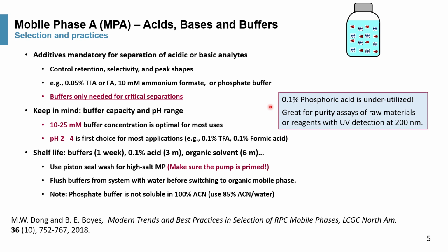I would venture to say that 0.1% phosphoric acid is probably underutilized and should be used more, because it's great for purity assay, for raw material or for reagent, with UV detection below 200 nanometers. So it's great for universal application at a low wavelength. Obviously, this acid is not a buffer, right? If you use a mass spec compatible buffer, then it is not possible to go down below 210 or 220.